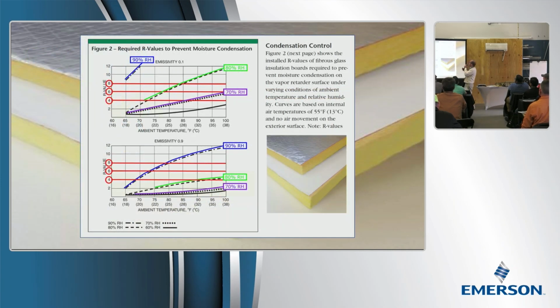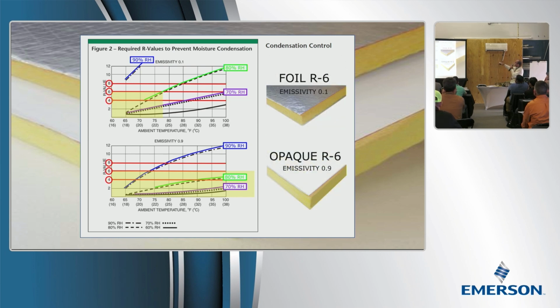The guys who make this stuff, NAIMA, remember when we started we said they can't touch 90% relative humidity. 90% relative humidity is going to sweat no matter what they do. Well, look what happens when it's dirty duct, when it's opaque instead of shiny. You can do 90% relative humidity at low temperatures, but it wasn't even on the chart. And you're golden with R6, the green one. Look, R6, you're great, and the only difference is it's not shiny. For people who do thermal imaging, it's about emissivity and how much heat it can give off. The foil insulation is like a thermal barrier, it reflects radiant heat. The opaque white stuff does not.